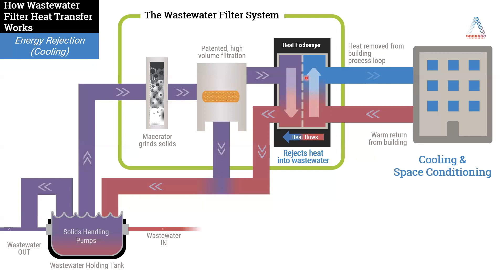So what we see in a lot of cases is getting into energy sharing, and this will hopefully illustrate the preliminary concept before I finally show the actual geofield tie-in. But in this case, what we're looking at is an overall system building loop that is looking to generally share energy. So in this case, we're probably looking at a number of different pieces of equipment within the building. You know, equipment on the south side of a building that might have a lot of thermal gain because it has some sun exposure, whereas the north side of the building will be in shade and will actually need heating.